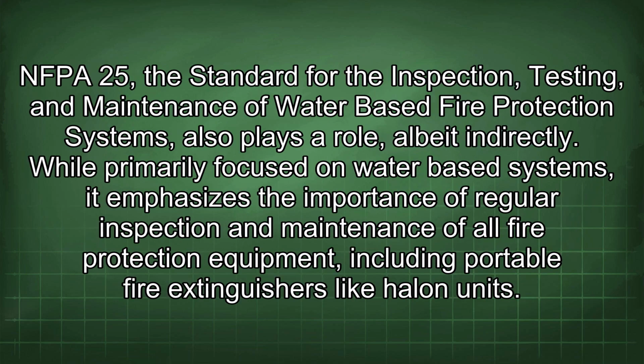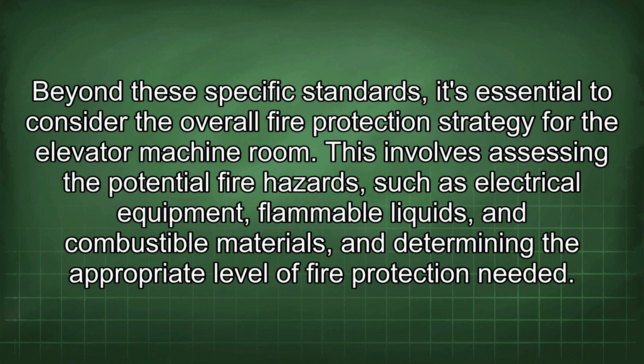NFPA 25, the standard for the inspection, testing, and maintenance of water-based fire protection systems, also plays a role, albeit indirectly. While primarily focused on water-based systems, it emphasizes the importance of regular inspection and maintenance of all fire protection equipment, including portable fire extinguishers like Halon units. Beyond these specific standards, it's essential to consider the overall fire protection strategy for the elevator machine room. This involves assessing the potential fire hazards, such as electrical equipment, flammable liquids, and combustible materials, and determining the appropriate level of fire protection needed.